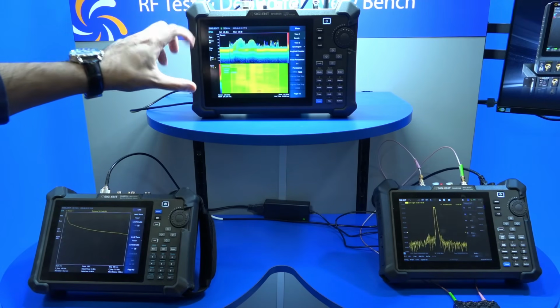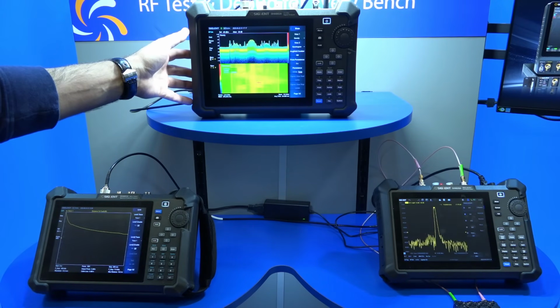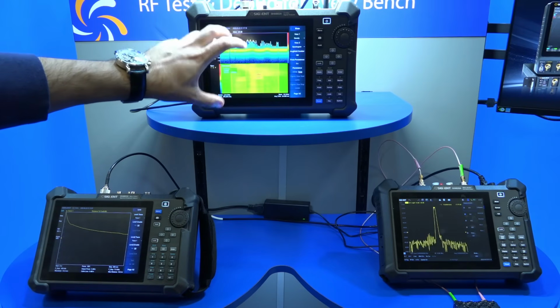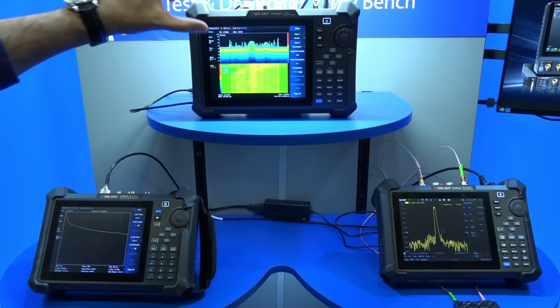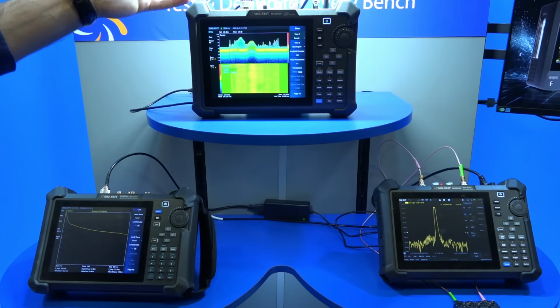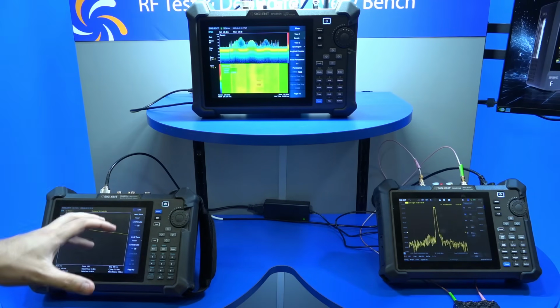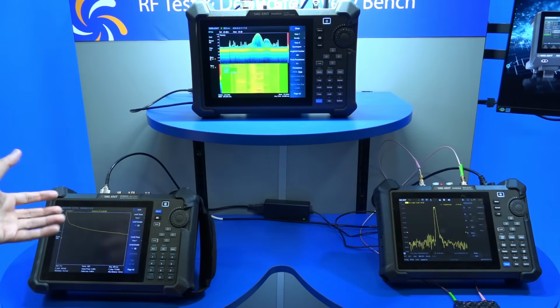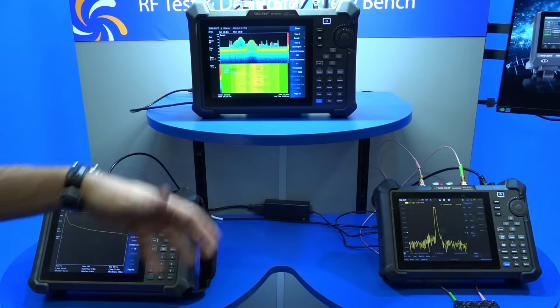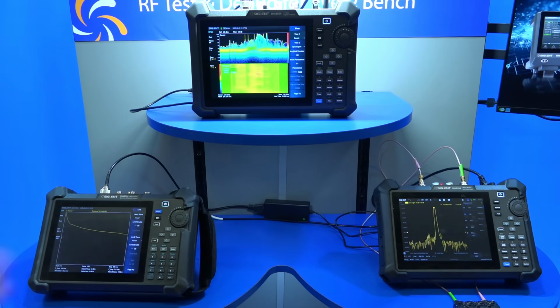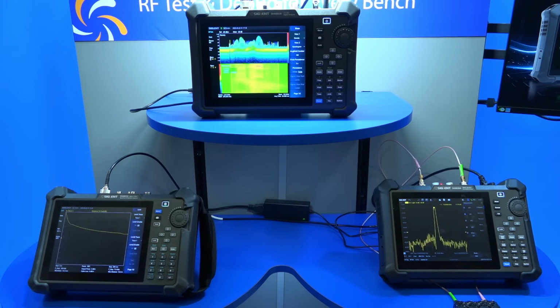Apparently, this is also going to eventually reach 26.5 gigahertz as well, but because it does have the real-time and that digitizer, it also does some streaming in chunks of memory, so you can stream data out and do demodulation outside of the instrument. But they have clearly taken the core technology in their spectrum and network analyzers and miniaturized them to some extent, providing all these handheld devices, competing with some of the bigger players in this domain.